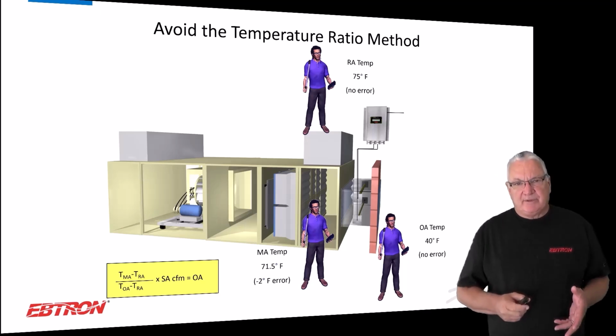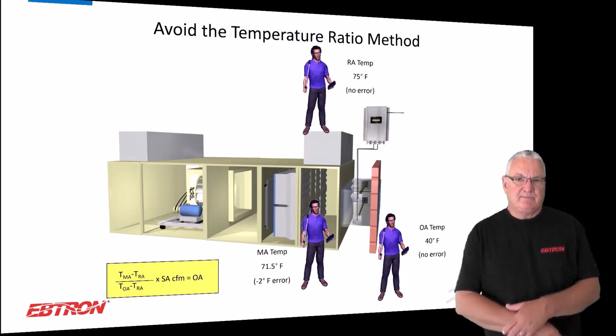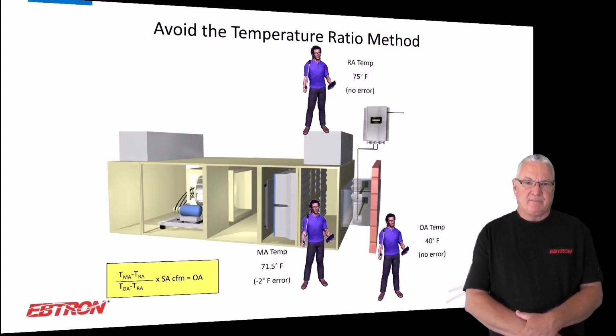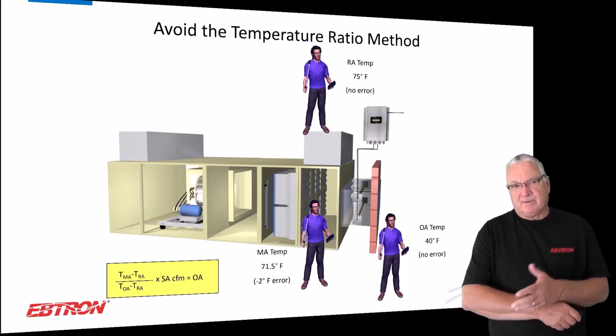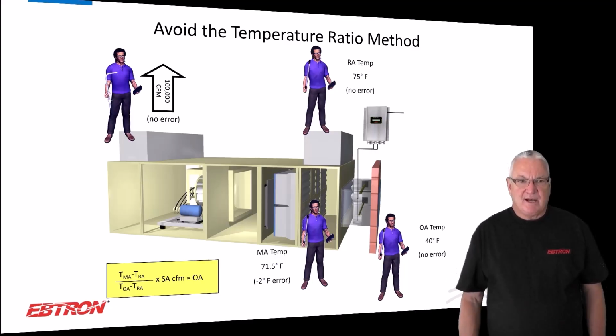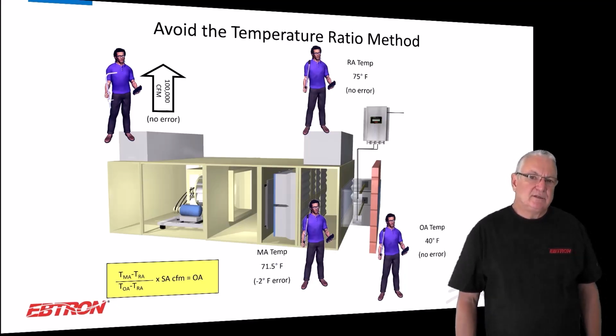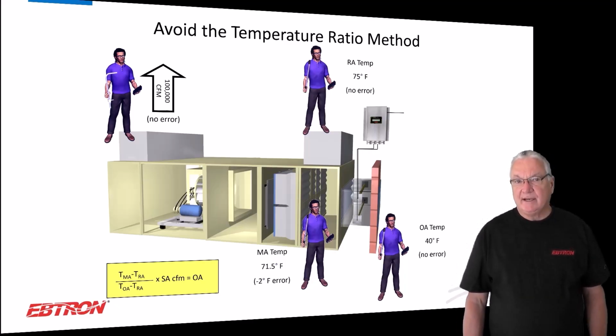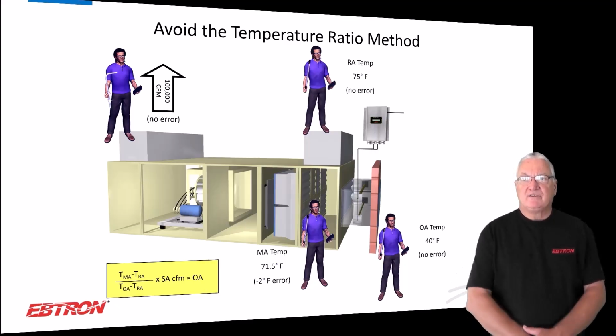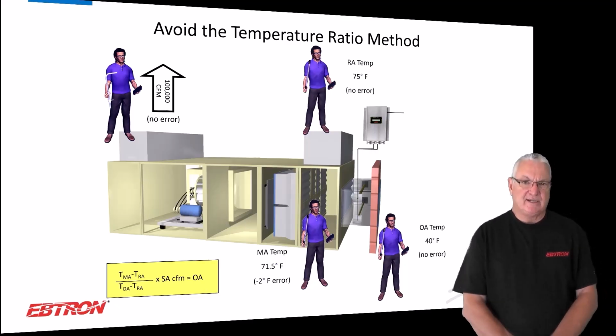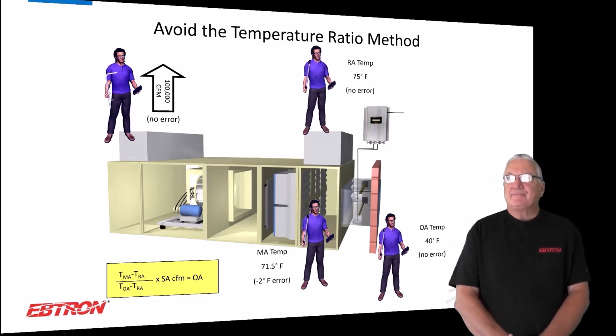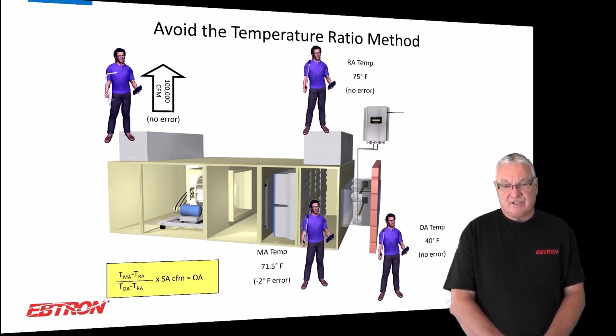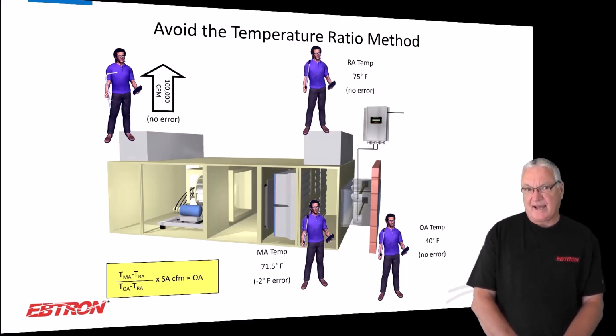With those three temperatures, you can use a very simple mixing equation and estimate the percentage of outside air in the mixed air, which is the supply air. Then if you measure the supply airflow rate, theoretically, you have the outdoor airflow rate. People have done this, and people are still doing it, but there are problems with this. I've heard people say, as long as the outside air temperature is far enough apart from the return air temperature, you can do it. But they're not looking at something real simple here, which is measurement error in general. Now, I'm going to make this better than actual.